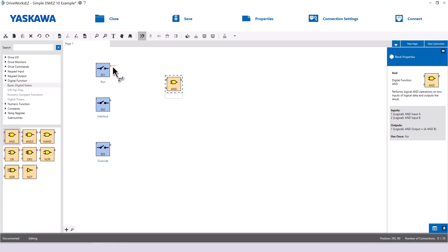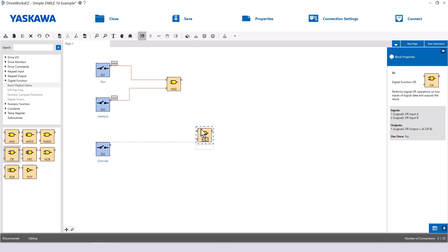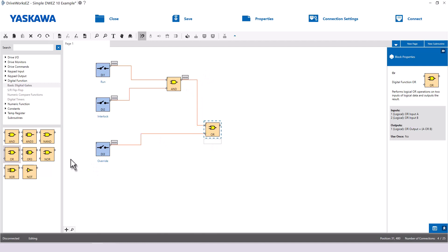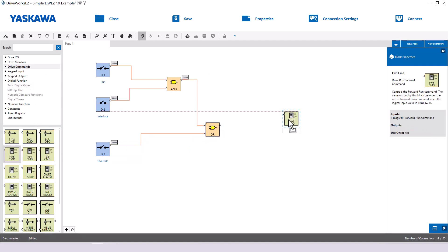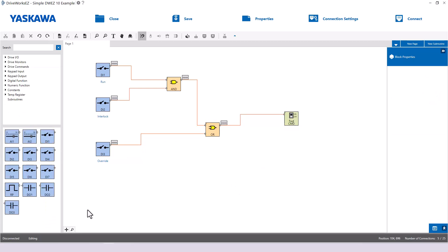The output of the AND block will be connected to an OR block. Our override input will connect to the other input of the OR block. The output of the OR block gets connected to the forward command block. Now, you will start to see what we are building here. If the run and interlock are both closed, or the override is closed, then the drive will run forward. Let's move on to the frequency reference.